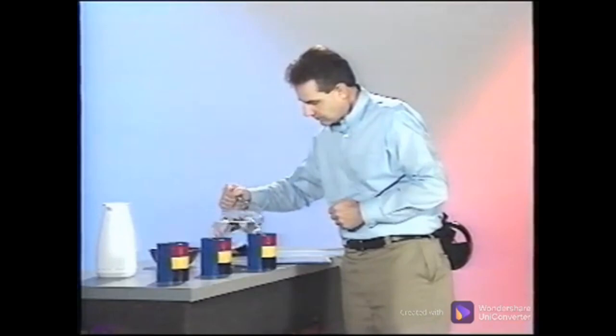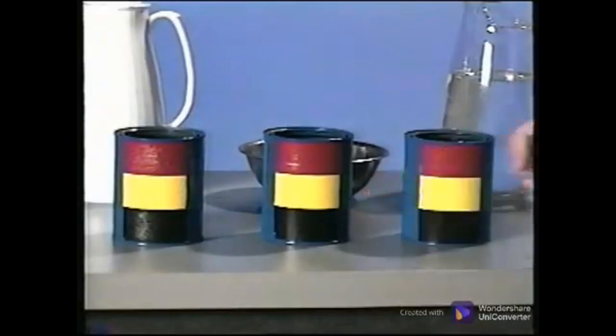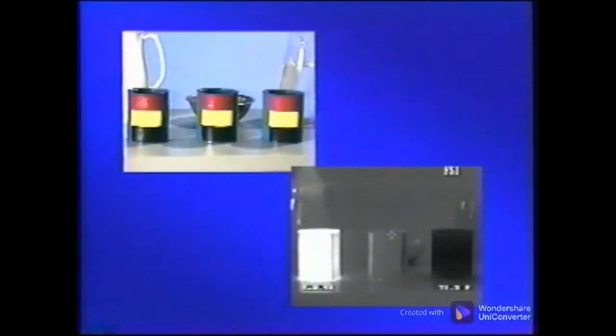Here the colors of tape are clearly evident using a normal camera that is sensitive to the visible light. Now the viewing screen is split, showing the visible light on one side and the infrared image on the other. Although the infrared image can be displayed in color, where the brightest or whitest spots indicate the hottest temperatures, most seasoned thermographers use a grayscale or black and white image to more accurately determine the levels of brightness. Here we are using a grayscale image, where the hottest temperatures are lightest and colder temperatures are progressively darker. So the hot can appears light and the cold can is dark.